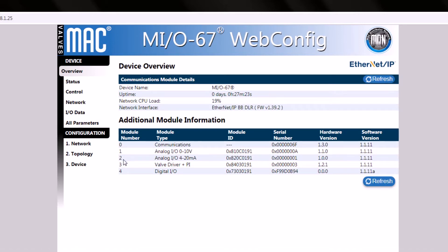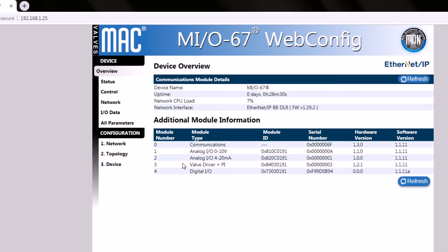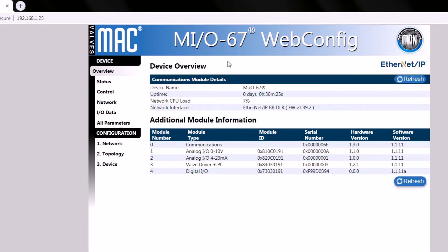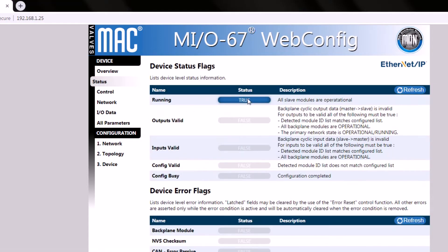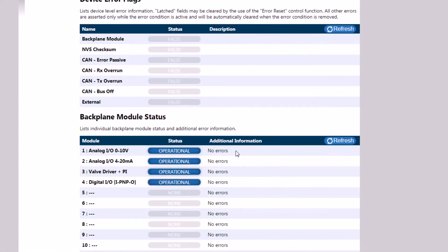In slot two, we have an analog I/O 4 to 20 milliamp amperage module. In slot three, we have a power plus module, also referred to as a valve driver. In slot four, we have a digital I/O module. We can also use the web config utility to check the statuses of the modules. The backplane module status shows that all modules are operational.